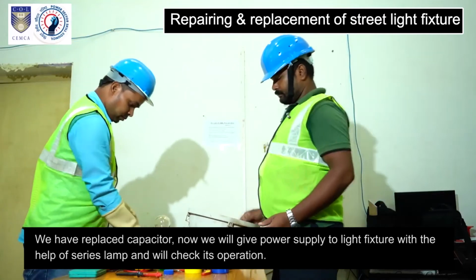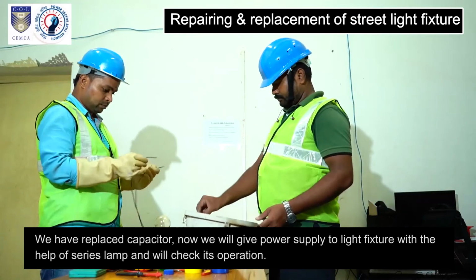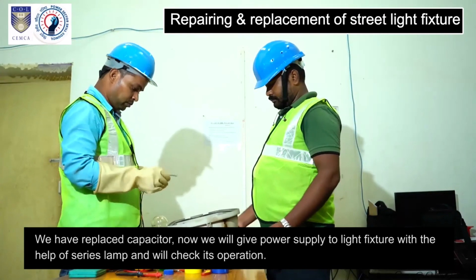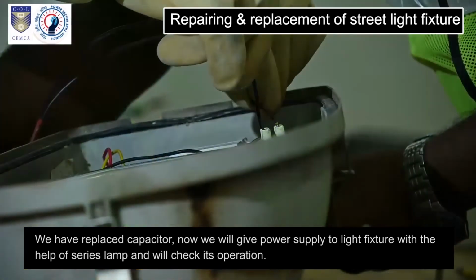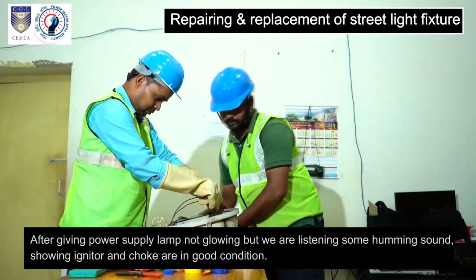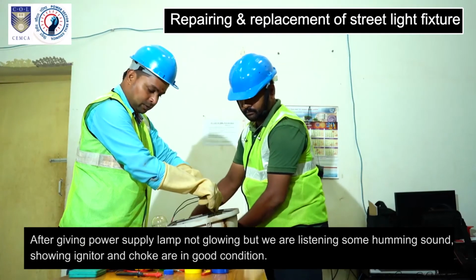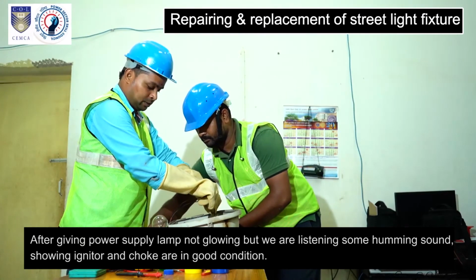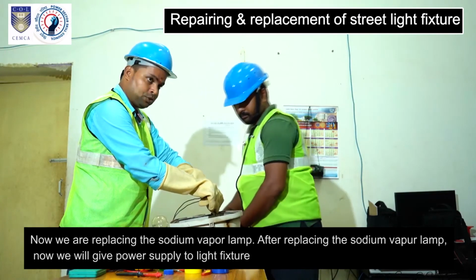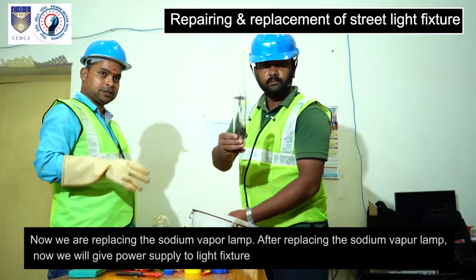We have replaced the capacitor. Now we will give power supply to the light fixture with the help of a series lamp and check its operation. After giving power supply, the lamp is not glowing, but we are hearing a humming sound, showing the igniter and choke are in good condition. Now we are replacing the sodium vapor lamp.